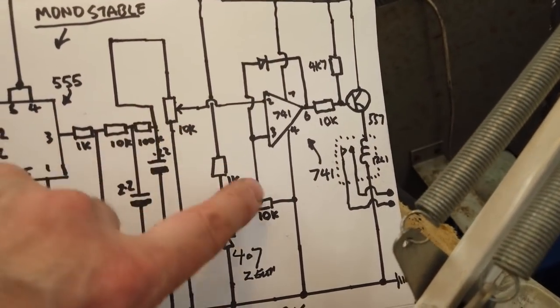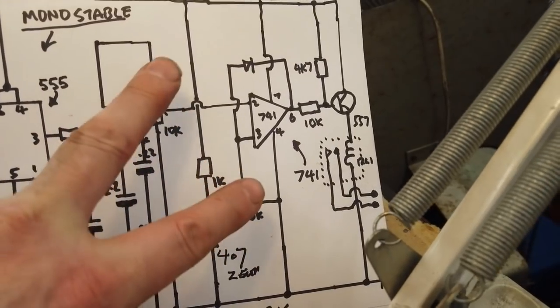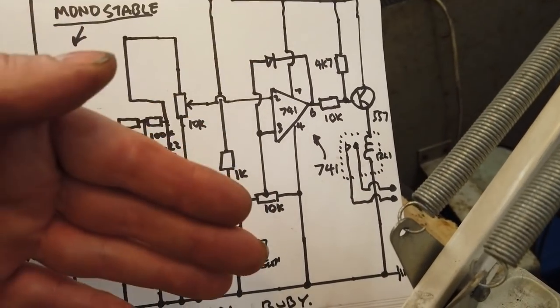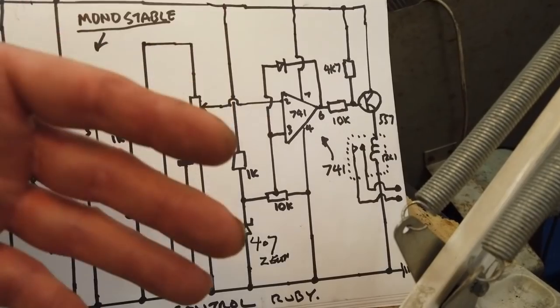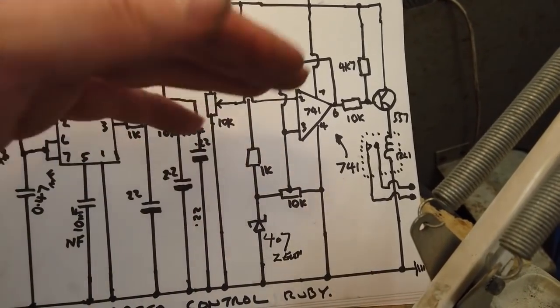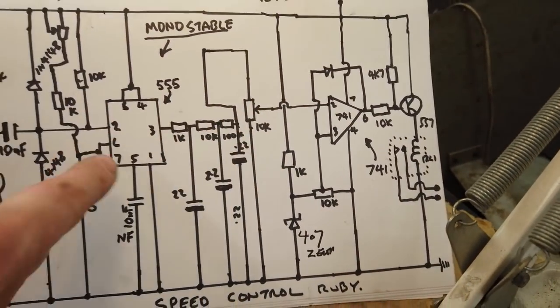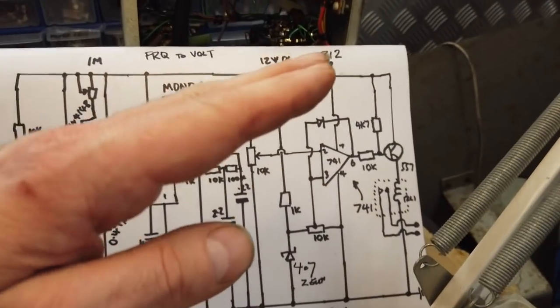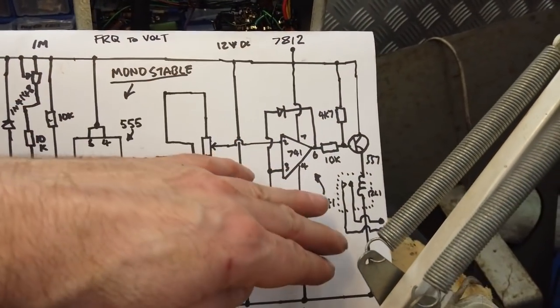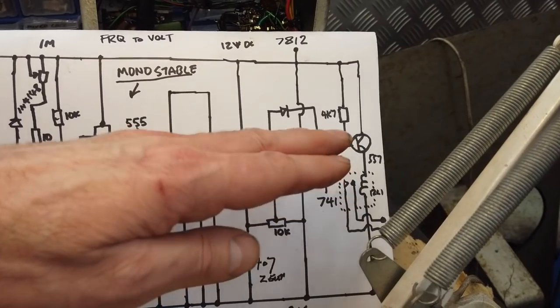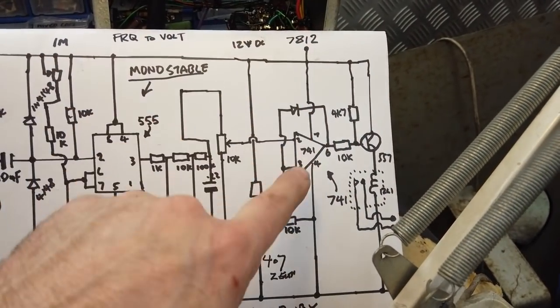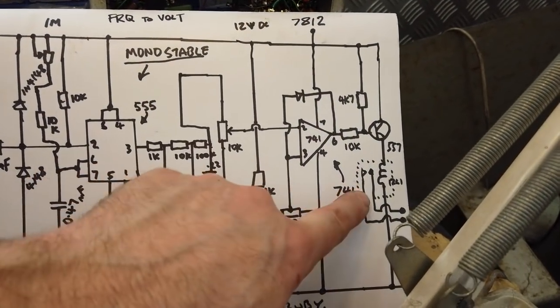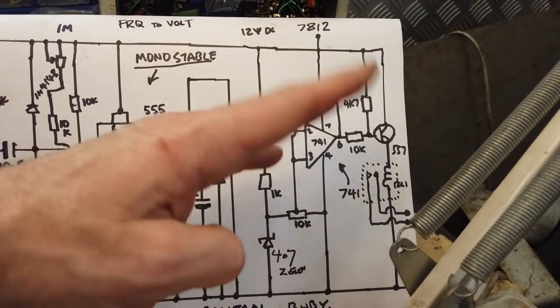That's called the hysteresis, the switching point between the two. So we get 2 switching points, on at 60, back off at 40. If you just had it on at 60, it's so accurate that as I went 60.59 or whatever, it would click out. Then as I go 60.6, so in other words, the minutest mile an hour change would have this relay going click, click, click, click, click.